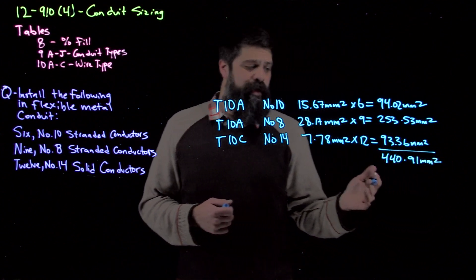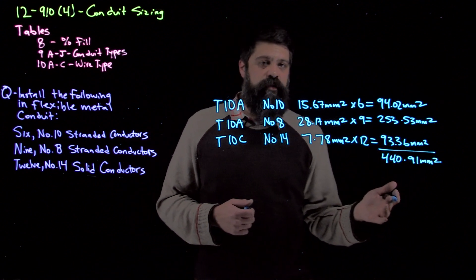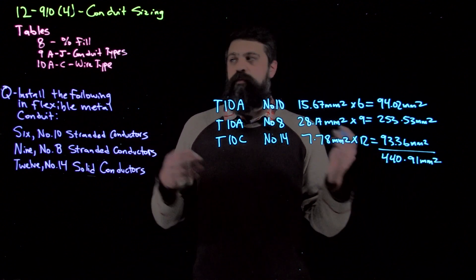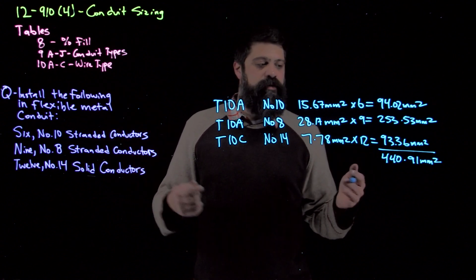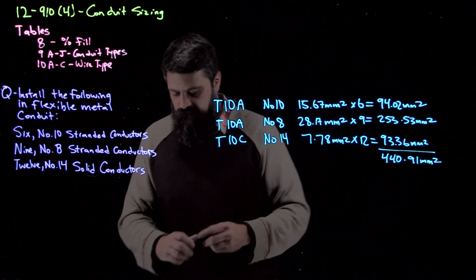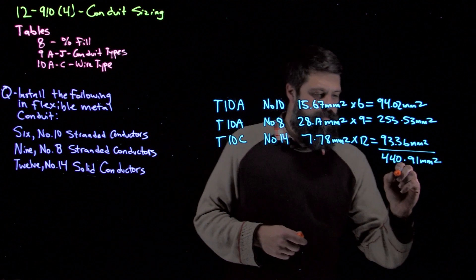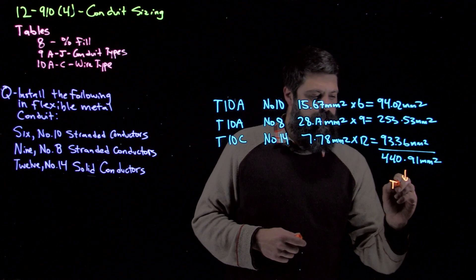Now we need to know the percentage fill that we can actually fill a conduit up to. That's where we go back over to table 8. When I have more than 4 conductors, I'm going to be into a 40% fill. All right, so take this down, table 8.